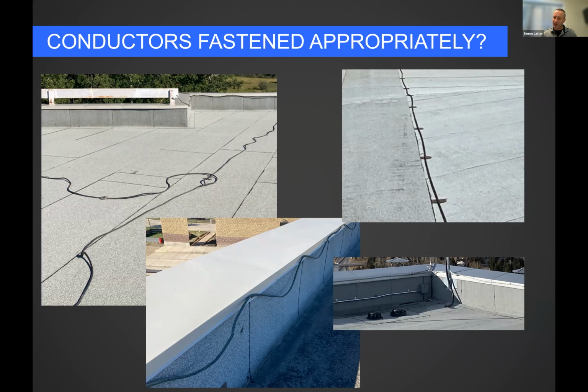If you shove 20,000 amps of current through a conductor in a matter of 60, 70, 80 microseconds, at the joints and at the bends, there is a significant electromechanical force. I've seen this at lab scale. There was enough force to just yank a conductor directly out of the clamp when the clamp wasn't fastened properly. So you want to fasten it down because you don't want it whipping around in the event of a lightning strike. That's going to cause damage to the conductor.